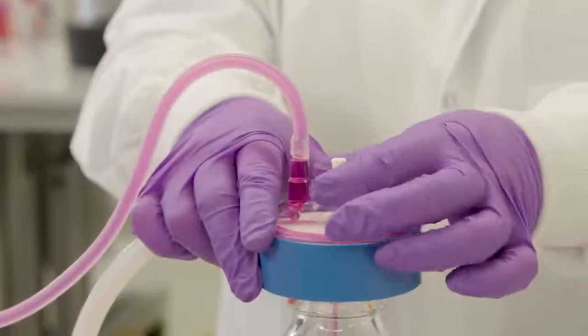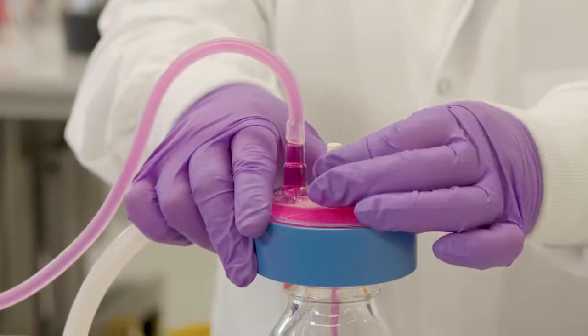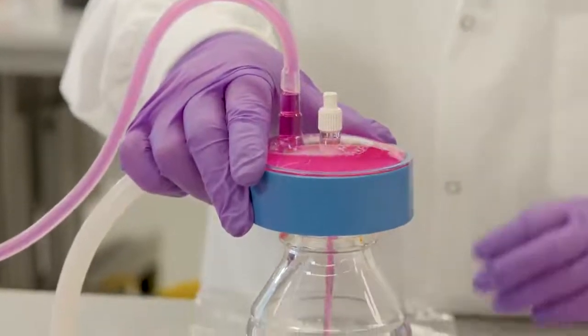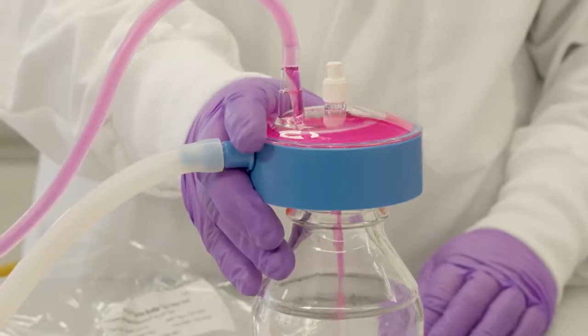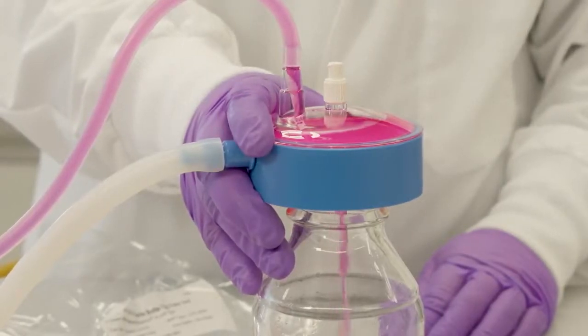Open vent port needle valve on the top of the unit to expel air until the filter is covered with liquid. A small amount of air collected at the top of the dome is normal and it will not affect filtration.